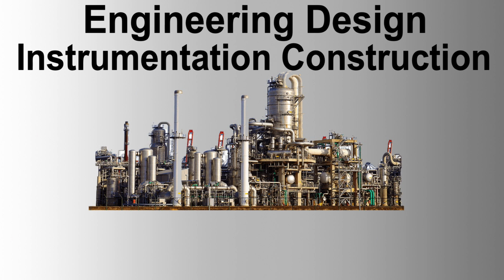The run of pipe and tube supports shall be determined with proper reference to the general layout of the installation to be served. Where the runs penetrate through the walls or floors, separating areas of different hazardous area classifications, the penetration shall be made using a proprietary transit frame and blocks to ensure and maintain the safety of the different areas. No unnecessary junctions shall be made in the tubing. This is in keeping with the specifications and good engineering practice. All supports shall have 25% free space. All cable trays shall have 25% free space.